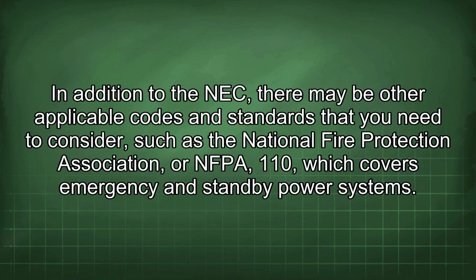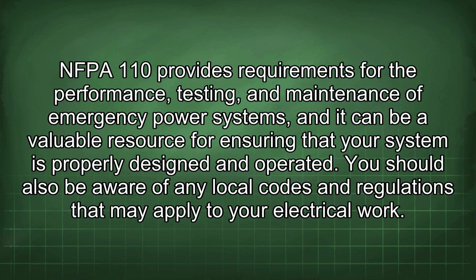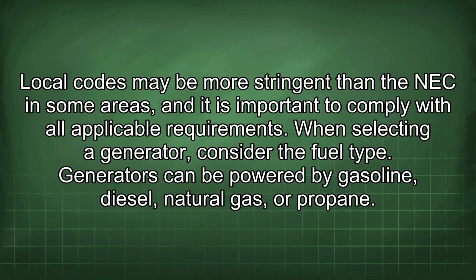In addition to the NEC, there may be other applicable codes and standards that you need to consider, such as the National Fire Protection Association, or NFPA 110, which covers emergency and standby power systems. NFPA 110 provides requirements for the performance, testing, and maintenance of emergency power systems, and it can be a valuable resource for ensuring that your system is properly designed and operated. You should also be aware of any local codes and regulations that may apply to your electrical work. Local codes may be more stringent than the NEC in some areas, and it is important to comply with all applicable requirements.